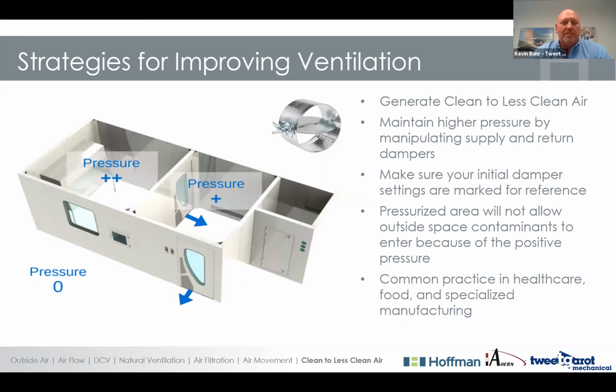This one's interesting, the verbiage of it: generate clean to less clean air. In our practice and reviewing this slide, it can be difficult to explain this one, and I'll give you an analogy, but it's to maintain higher pressure in some occupied spaces than in surrounding spaces. And you can do this by manipulating the airflow in your system.